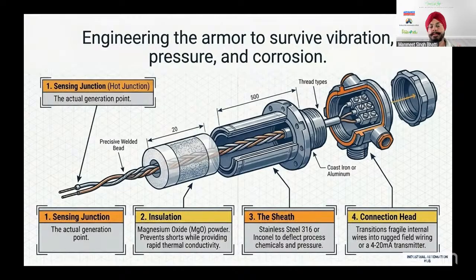Second point is called the insulation. Because it's a metal over here, it may cause shorting. So for insulation, we put magnesium oxide powder. There is a tube, and inside the tube we put a thermocouple, and the thermocouple has the insulation of MgO. That is always put in over there. And after this MgO, you will find the sheath. The sheath is SS316 or whatever the metal compatibility of the process requires. It can be Inconel also, it can be titanium or tantalum also, based on that. The sheath is a tube which can handle that pressure and that vibration, through which the sensor goes, and in which we put magnesium oxide, filled to the brim, right to the end.